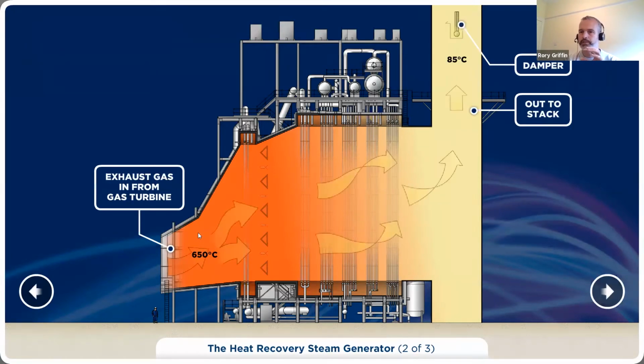So the 9FB machine we have is quite tough on the first stages of tube bundles, which is our high pressure superheater. So part of our maintenance inspections is we always go in and have a look and see is there any bracing needed or how are the baffle plates, because you don't want the hot gases escaping on the side of the tubes because you'll start getting differential heating on the rest of your tubes here. So it's a horizontal flow boiler with vertical tubes. There's 18 modules in total.